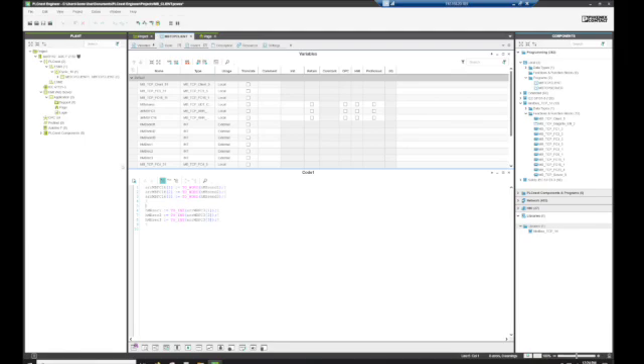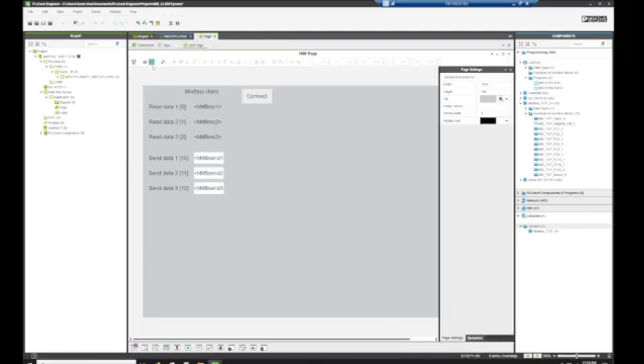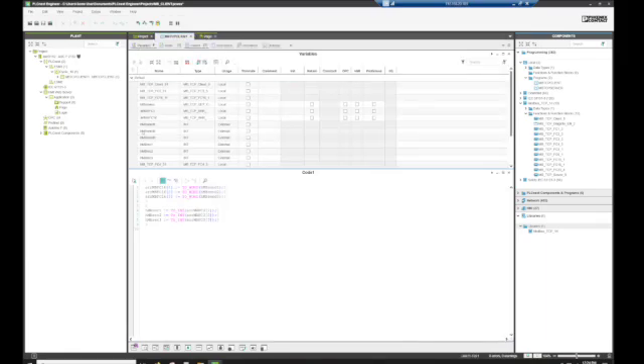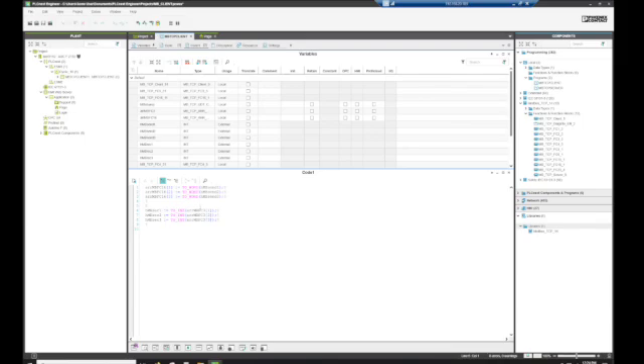It did do a little bit of movement of the arrays just so that we can see the data in a readable format on say the HMI screen like this. So that way we can actually see what data we're sending and then read the data that's being sent to us. Basically I'm just saying take the first three elements of function code 16 and put in these three variables. And then read from function code 3 the first three variables. Now I will say in the server block the array element starts at 0 and in the client blocks the arrays start at 1, so just keep that in mind when you are doing it. Zero is an invalid call to the array.